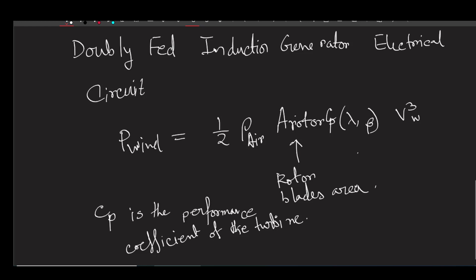In a double-fed induction machine, unlike a standard wound rotor machine, the stator windings are directly connected to the grid, and the rotor winding is connected to the grid through a converter. This AC-DC converter divides into two components: the rotor side converter and the stator side converter.